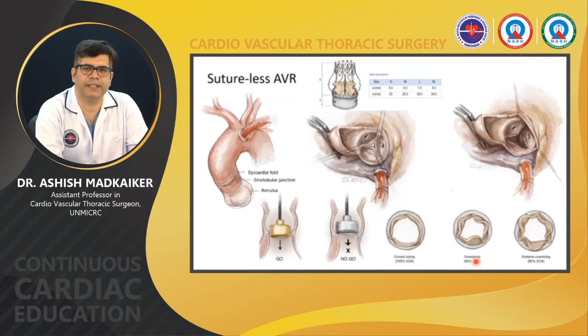If it goes in too freely, then we should move on to the next size. At the same time, we should not oversize a sutureless valve, because this illustration demonstrates that an oversized valve may not open or may not expand well, and as a result the valve is not opening properly and can result in significant reduction in effective orifice area.